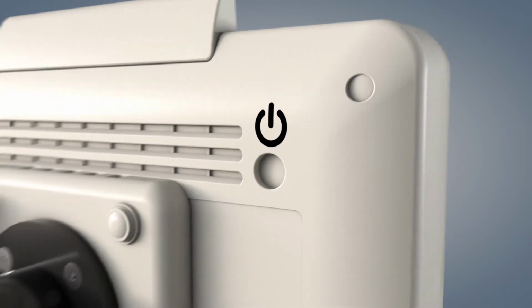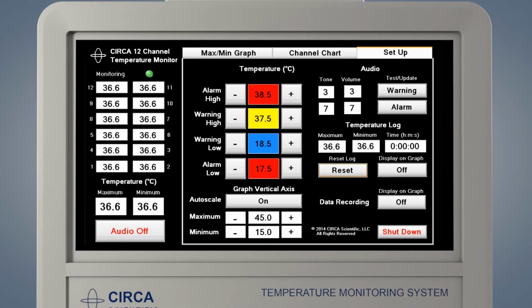upper right corner. The program may take up to 2 minutes to start. When the monitor is first switched on, the setup screen will be displayed within 2 minutes. Assure that appropriate temperatures are shown on all 12 sensors. From this screen, you may also set warning and alarm limits and adjust the volume, among other functions. The monitor is also shut down from this screen.